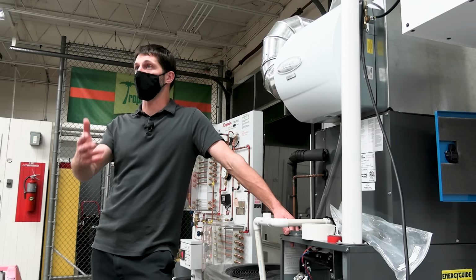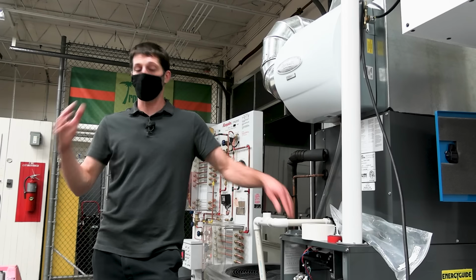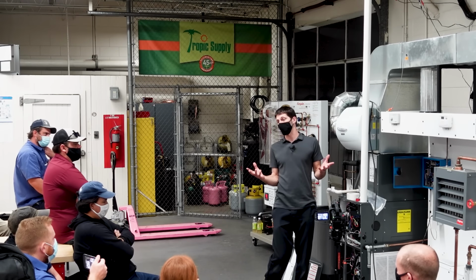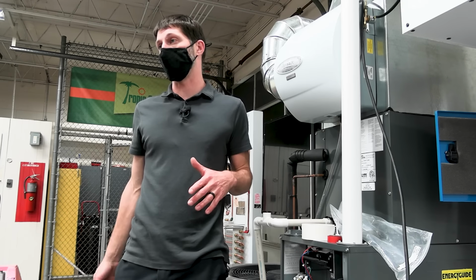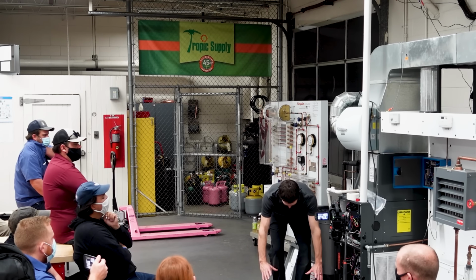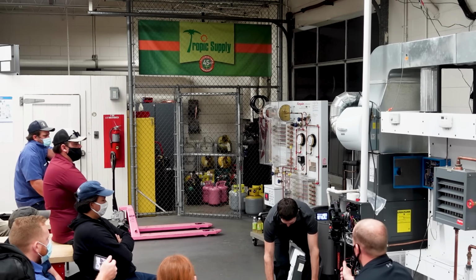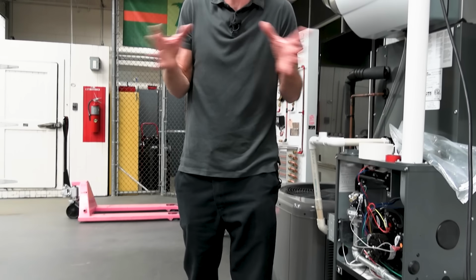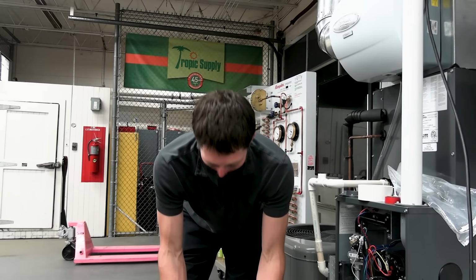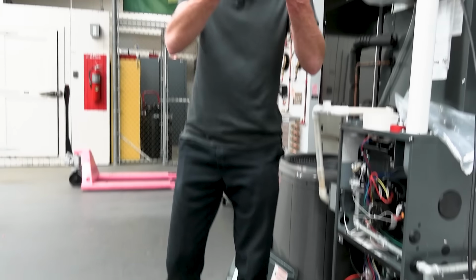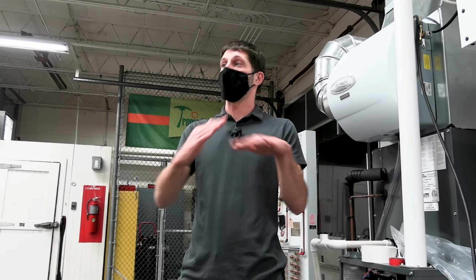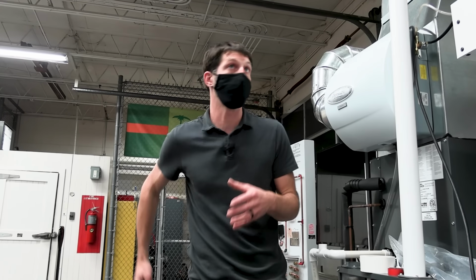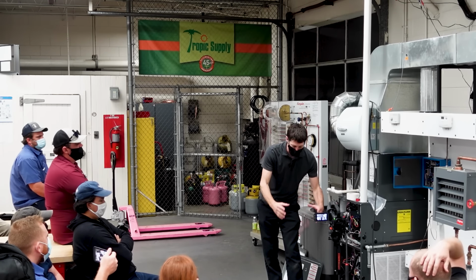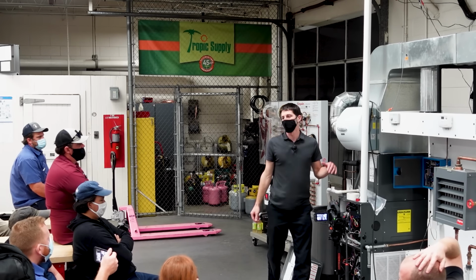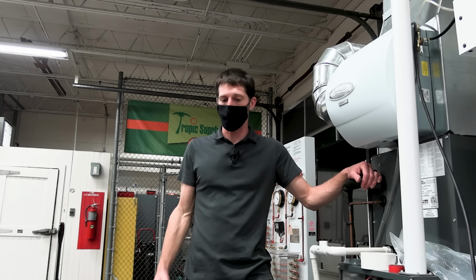Realize also on a water heater, you do have cold air rising and mixing with the exhaust gas, and that's actually supposed to slow down the exhaust from rising too quickly as well. You know, you have a baffle in a standard natural draft water heater where the exhaust is naturally drafted. You have a baffle that tries to slow down the exhaust from rising too quickly. And then you have the cold air that comes in as well, and that's also there to slow down the exhaust. Otherwise, it's just going to skyrocket right through that without the heat exchange from the exhaust to the water jacket that's surrounding it. That's the premise, I guess, of the old natural draft boilers, water heaters.